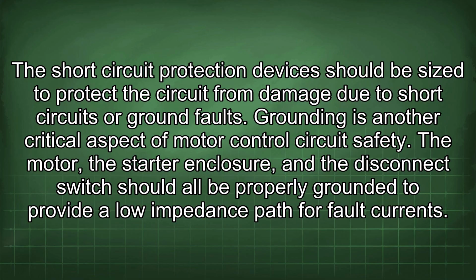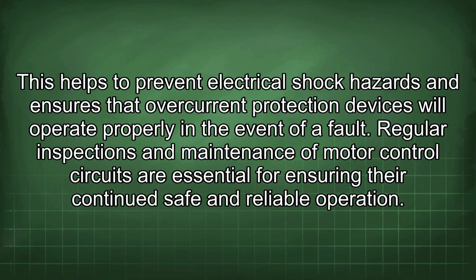circuit breakers. The short-circuit protection devices should be sized to protect the circuit from damage due to short circuits or ground faults. Grounding is another critical aspect of motor control circuit safety. The motor, the starter enclosure, and the disconnect switch should all be properly grounded to provide a low impedance path for fault currents. This helps to prevent electrical shock hazards and ensures that overcurrent protection devices will operate properly in the event of a fault.